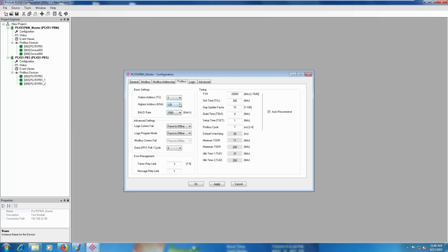From a Profibus perspective, you can set your highest station address, you can set your baud rate, and you can set some of the failure status, meaning how you want to set those Profibus outputs, the data on that side, if you lose communication on the Logix side. There are some advanced features for Profibus timing on the network. We typically recommend sticking with the auto recommend settings unless you've got an application that requires some changes to either the quiet time, TSET time, or slot time interval, things like that.